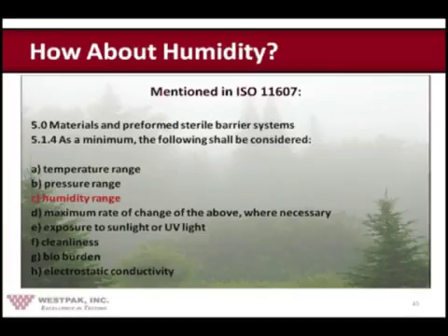So what 11607 says about humidity is consider it, just like you would rate of change, maximum rate of change, exposure to UV, cleanliness, bioburden, electrostatic conductivity, lots of different things. So consider it. It doesn't say do it. It says consider it. Okay? I thought that was an interesting way to handle it.